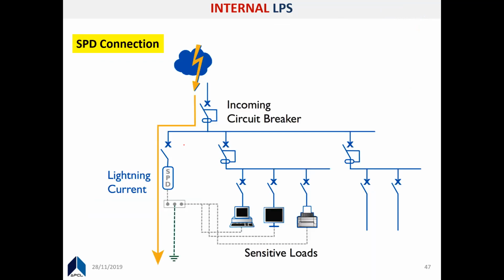So you can see, when you get a lightning strike conducting downwards, this is the external LPS, not the internal, external LPS. This is a separate one, but now you have the electrical installation as well. If you have these together, then you will have a problem, but it's eliminable. There are solutions and measures to practice. So if you have it, then you had better keep it afar, at least like 20 meters, let's say.